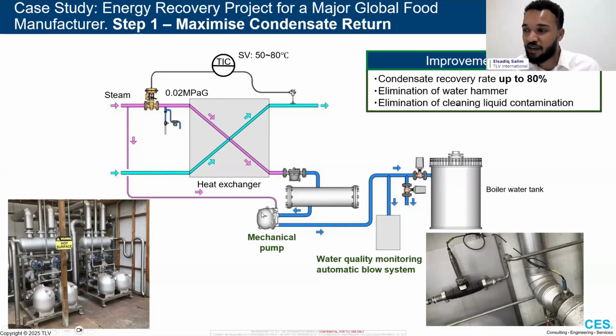Many manufacturers have mechanical pumps or pump traps that are designed to discharge condensate when there is enough pressure naturally. And when there's not enough pressure, they'll collect the condensate and use higher pressure steam to push that condensate all the way back to your feed water tank. Very common solution, very well established in the industry. And the key message there is that where you're not returning condensate, explore the solutions that might be available to allow you to return that condensate without affecting your heat exchanger or your application, because that's always going to be the priority. A solution that affects your heat exchanger is not a solution at all.